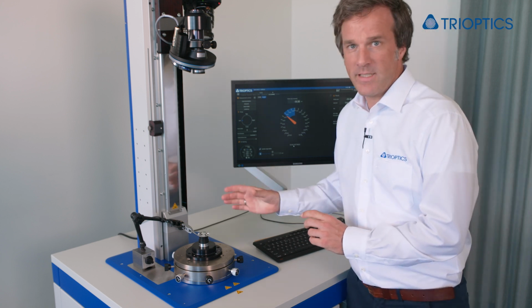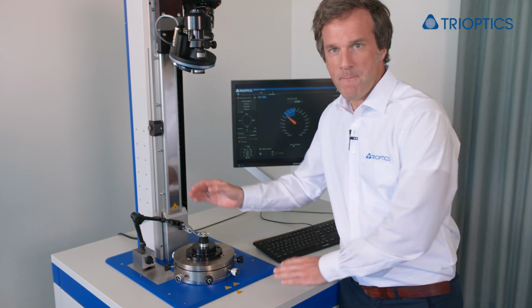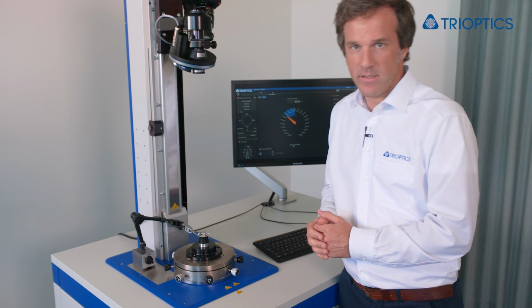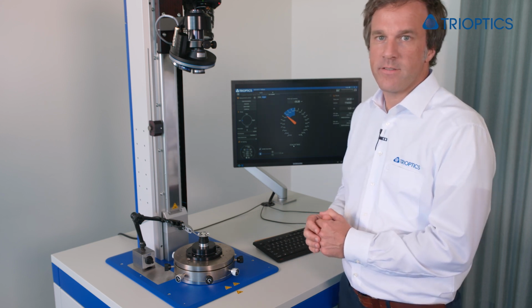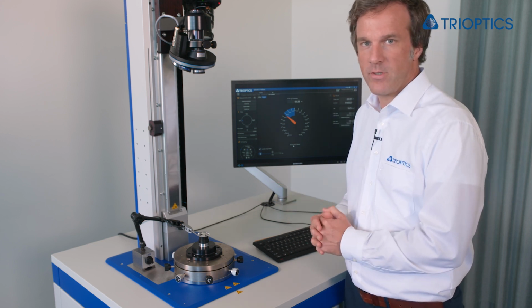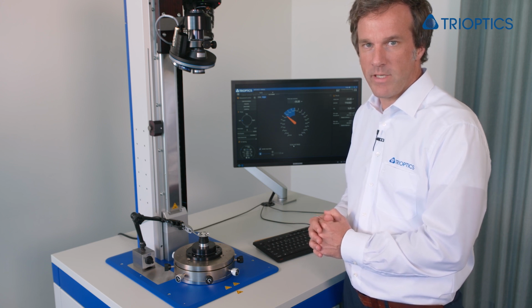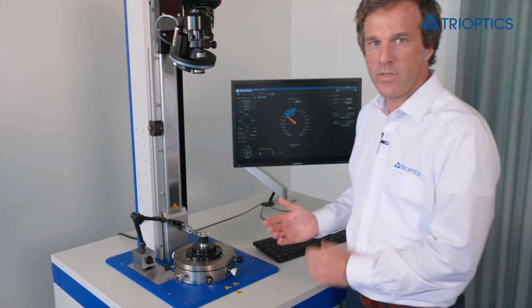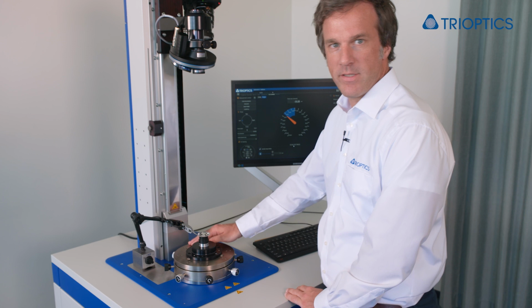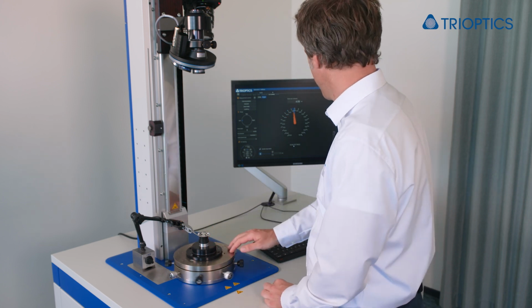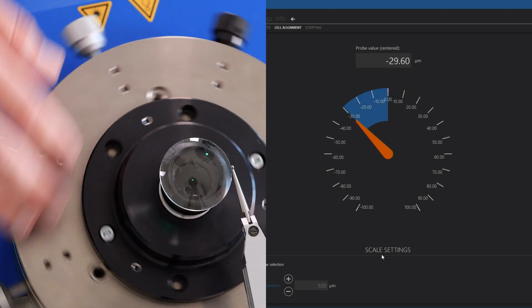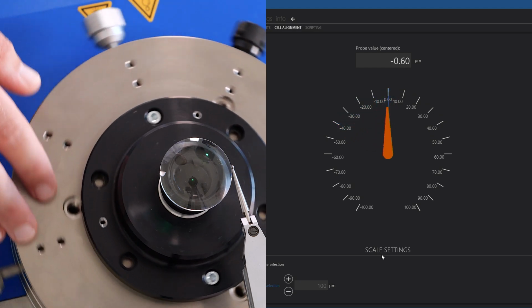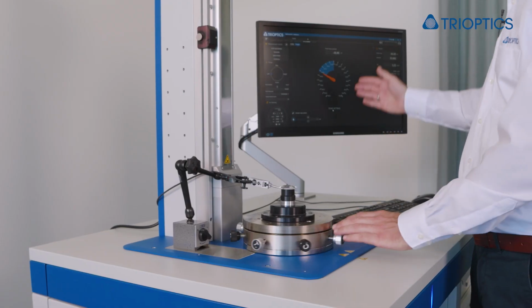We have this single lens here on this pre-centered chuck and use a dial indicator. I could also use an optical distance sensor to read the runout of the lens when it rotates. I can simply do this by hand, so I let the air bearing spin. And the software directly displays the live values of the indicator.